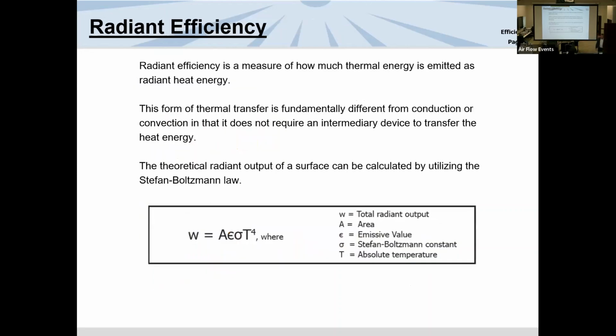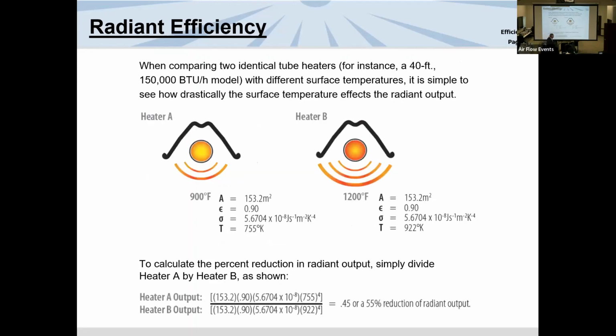Next slide. Radiant efficiency. This formula used to throw me for a loop. I still have to reference it, but radiant efficiency: total radiant output is equal to A, the area. How big is the pipe? Okay. E, the emissive value. What color is the pipe? The Stefan-Boltzmann constant, which is a math thing to make it work, temperature to the fourth power. So how much pipe? What color is the pipe? How hot is the pipe? Really that simple. But you can put it to a mathematical formula by doing this right here. And we do. Next slide.